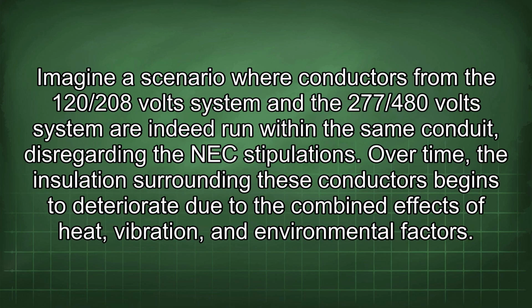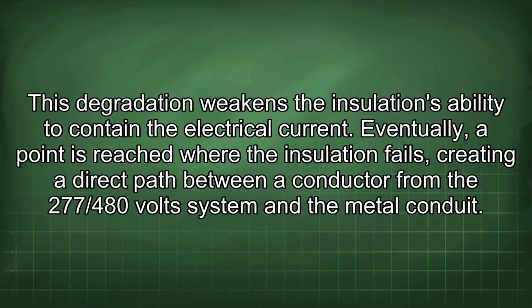Imagine a scenario where conductors from the 120/208 volt system and the 277/480 volt system are indeed run within the same conduit, disregarding the NEC stipulations. Over time, the insulation surrounding these conductors begins to deteriorate due to the combined effects of heat, vibration, and environmental factors. This degradation weakens the insulation's ability to contain the electrical current.